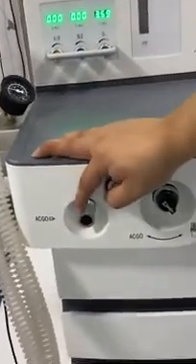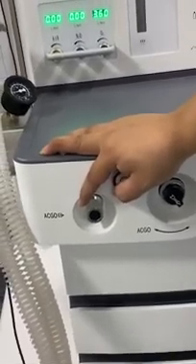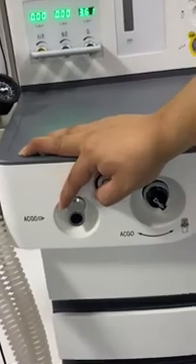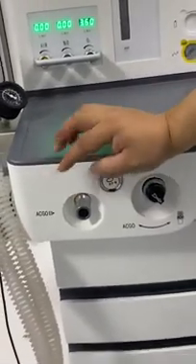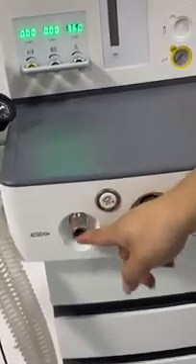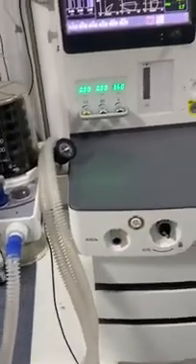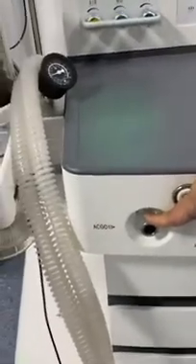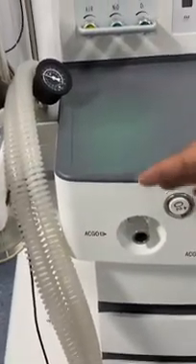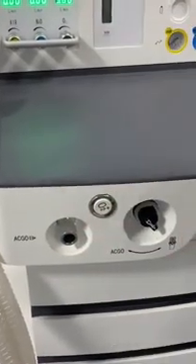And the second one is that when a patient comes to the hospital suddenly, immediately the doctors need to give them an operation, and they don't have time to judge if the patient has an infectious illness or not, they can also use this line, so it will not influence the main pipeline. And after the operation, you can just clean here, it is okay. The third function is that this port can realize the open circuit for operation. So if you want to use the open circuit for this anesthesia machine, you just connect the device here, and then we can do the open circuit.